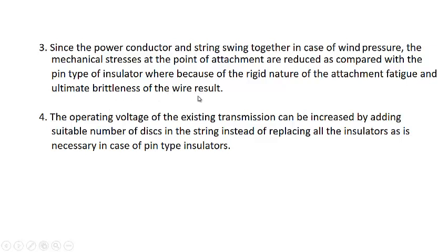In this case, in the pin type insulator, since the pin type is fixed, when the conductor moves, it results in a higher pressure or tension on the insulator. But in this case, since it moves with the conductor, there will be less mechanical stress at the insulator. The operating voltage of the existing transmission line can be increased by simply adding the suitable number of discs in the string instead of replacing all the insulators as necessary in case of pin type insulator.